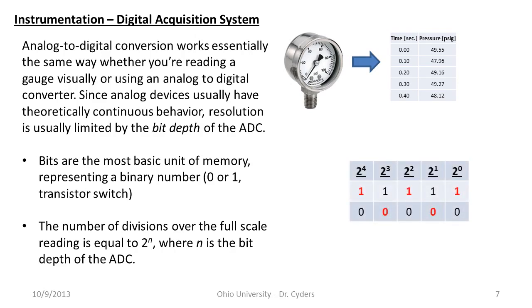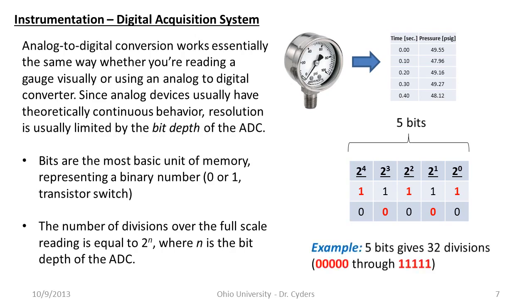Here's an example with five switches representing 2⁰, 2¹, 2², 2³, and 2⁴. With five bits, we can represent up to 32 divisions — 2⁵ = 32. If we evenly space those over our reading range of 0 to 5 volts, we can determine our effective resolution. Five bits gives 32 divisions, from 00000 through 11111. So how do we get from an analog signal to discretized digital data? Say we have our 0 to 100 psi pressure transducer outputting 0 to 5 volts. A 3-bit ADC gives 2³ = 8 bins — we use 3 bits here just so it's drawable on screen; in practice you'll almost never see fewer than 10 bits.